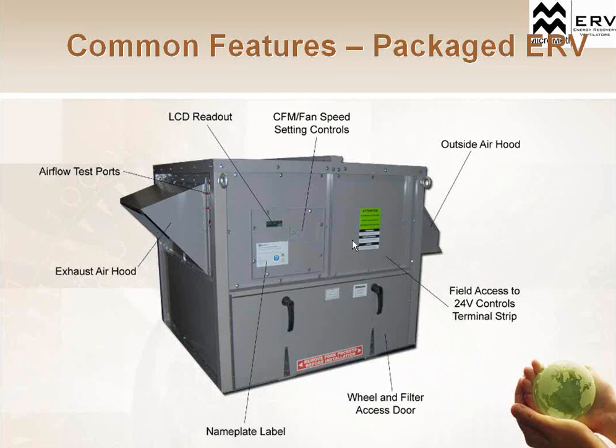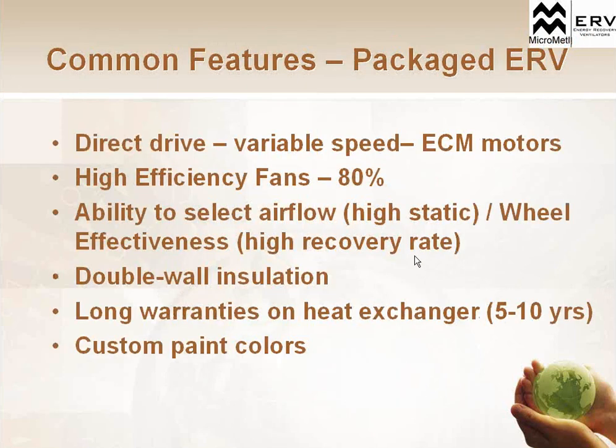We've got our supply and return exhaust flows with our hoods here, and our controls or fan speed settings. We'd actually use a roof curb type system in most packaged ERVs; we'll talk about that curbing system in a second. With most packaged ERVs, they can be direct drive or variable speed or even an ECM type motor. Usually high efficiency fans are used. We have the capability to dial in the amount of airflow in the system, allowing us to balance the airflows. We can adjust the wheel effectiveness, taking the higher recovery rate based on the CFM of the system. We can do a double wall insulation on the ERV itself.